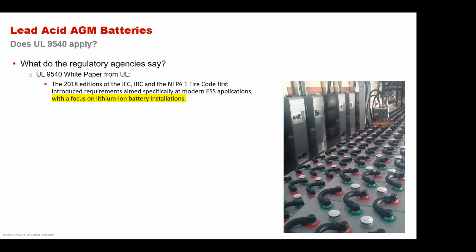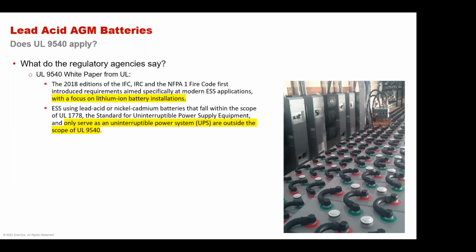Okay, so anyway, the focus was on lithium batteries, and reading further in that white paper, it says that energy storage systems using lead acid or NiCad batteries that are within the scope of UL 1778, which is a standard for uninterruptible power supply equipment, and only serve as a UPS, are outside the scope of UL 9540. So this is like a lot of telecommunication sites. They'll run on 48 volts, right? And they've been doing this basically since the telephone was invented.